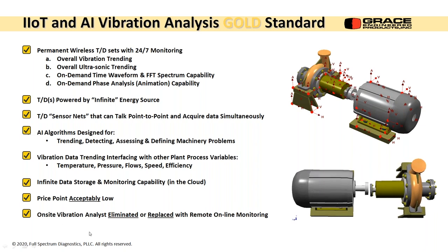This last one is that the on-site vibration analyst is eliminated or replaced with remote online monitoring. I think we're not there yet. That might be in the future. There might be just smart algorithms that will tell you when your machine's going to fail, but vibration is so subtle sometimes, and there's multiple things that happen, and it defies linear logic sometimes. But the more transducers you have, if I had 24 transducers on my machine instead of 4, I could do a lot more. So it all depends on pricing of transducers and how they can link together and acquire data.